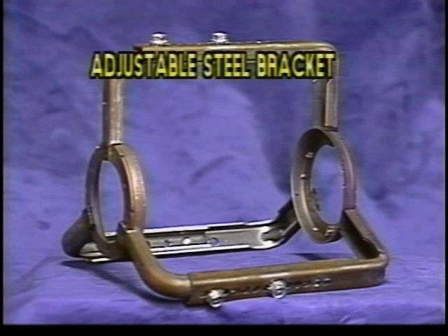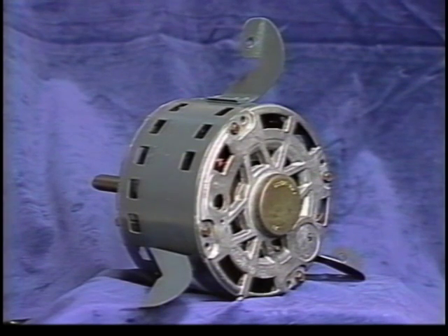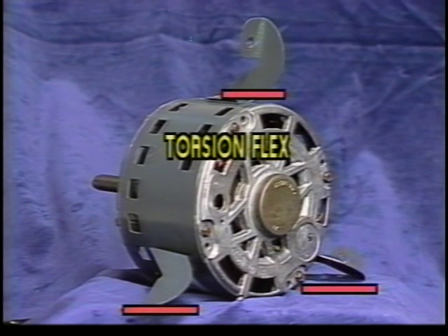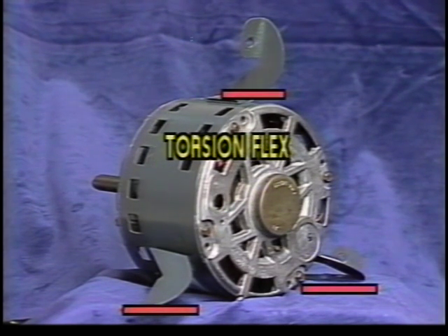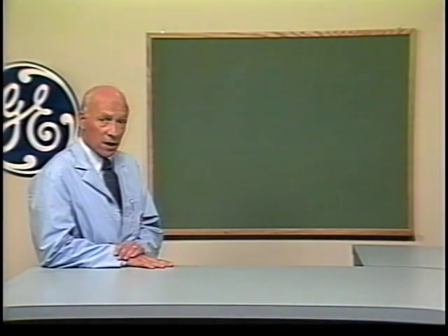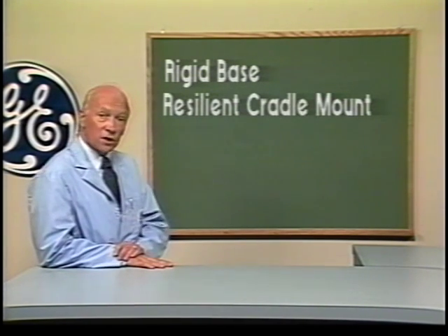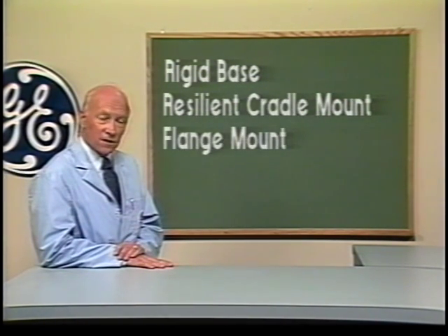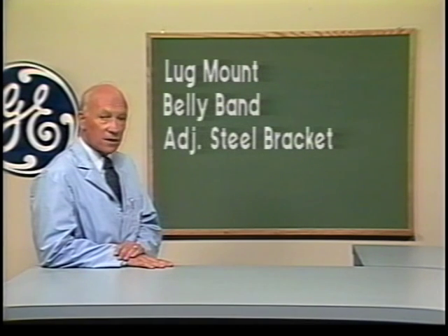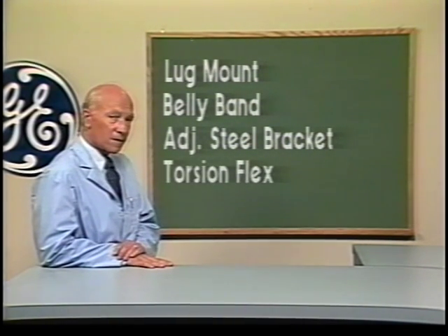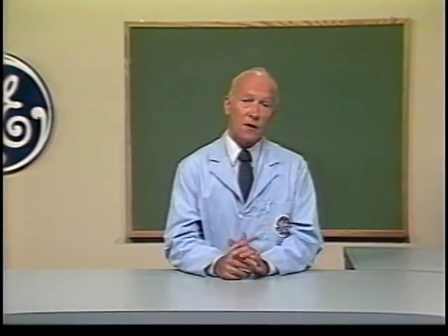Next is the adjustable steel bracket mount, which can be adjusted to accommodate different motor lengths. Finally, there is the torsion flex mount, which consists of three specially designed welded steel arms. The special steel and shape of the arms provide superior vibration and noise isolation, and also provide for a quick and simple installation. The eight types are: rigid base, resilient cradle mount, flange mount, extended through bolt, lug mount, belly band, adjustable steel bracket, and torsion flex.